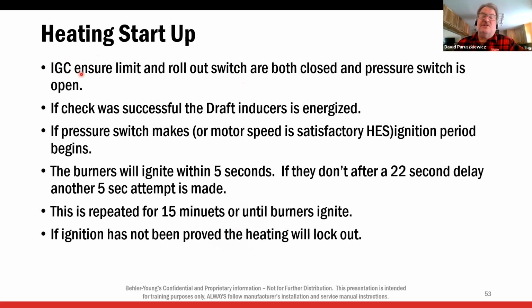The IGC is going to ensure at that point that all the limits are closed, the rollout switch is closed, and that we have no flame signal. So we make sure that all those limits are closed. The inducer comes on, the draft switch closes, sends a signal back. If it is the old Hall effect sensor, we're going to send a voltage back. We'll talk about that in a minute. The burners will ignite within 5 seconds. So these are direct spark starts, gas valve opens. If they do not light after 5 seconds, they shut down. There's a 22-second delay, they'll try again.